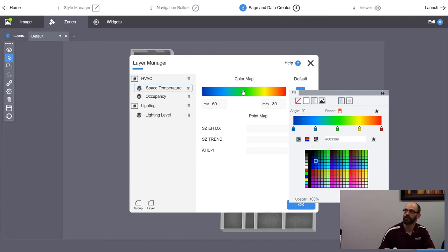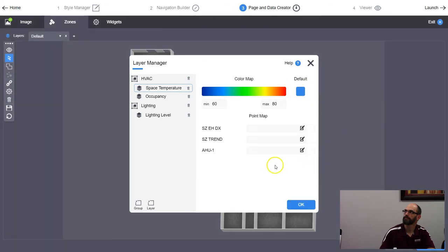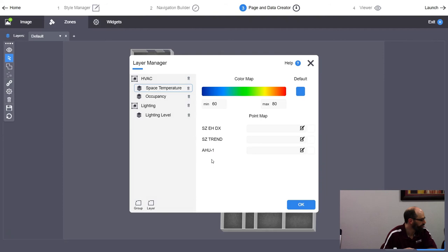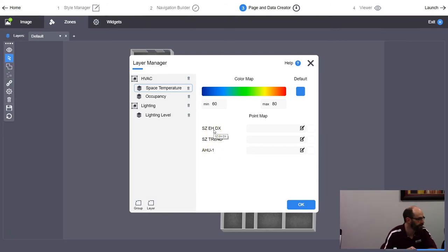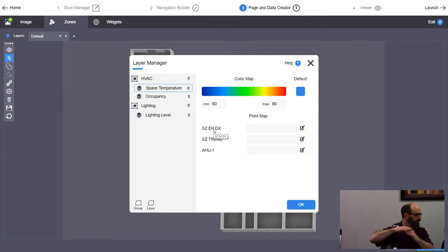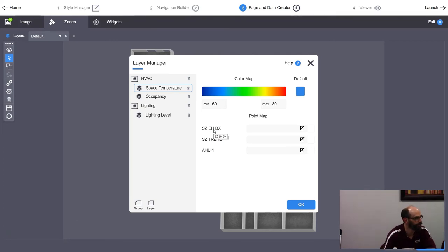You can adjust the color gradient for the layer. Down in the list you'll see the templates we created — AHE1 and the Single Zone Electric Heat DX template. This is where you tell it what point to display for each template when showing this floor plan layer. I'll set space temp for both templates. You can see the colors changing as the sine wave moves.